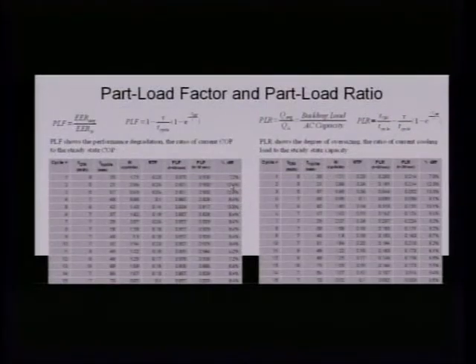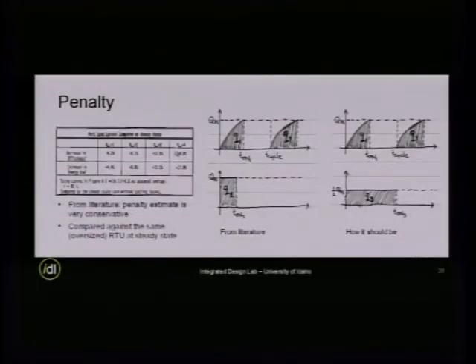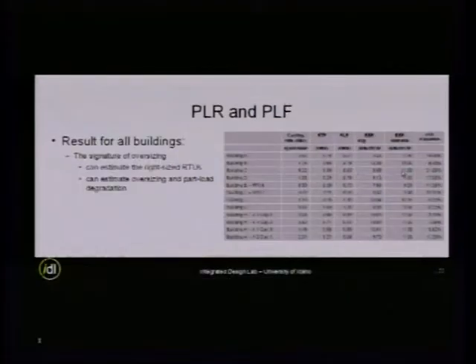So we calculated this too, and as you can see, our measurement has about 12% maximum, with a range from 12% down to a minimum of about 6%. Compared to the old literature, which says 14%, 15% efficiency degradation, this is confirming the old data. Another one is the part load ratio, the degree of oversizing. Over here, the part load ratio is 21%. It simply means that the air conditioning unit runs only 20% of its total capacity, which is bad. It's way oversized.